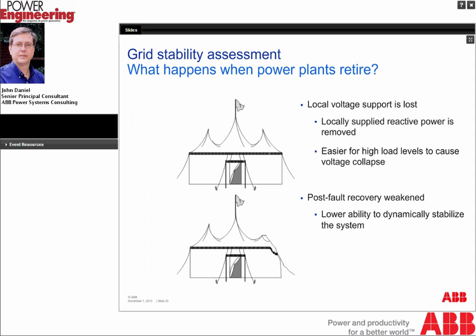Voltage stability and support is also impacted. The local voltage support is lost, and this can be related to, say, a tent with several tent poles, with the generation holding up the voltage around it. When the generation is retired, a portion of the tent is not supported as well. This will increase the stresses on the other parts of the tent, but it won't necessarily cause it to collapse, although it could. So it's important to understand how the voltage support in the area is lost or weakened. The other impact here is that post-fault recovery of the system will become weakened because there's less of an ability to dynamically respond and to help stabilize the system.